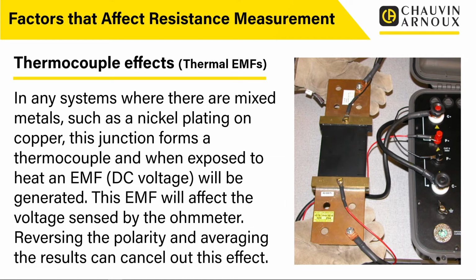Many testers, many micro-ohmmeters, include this automatic reversing function. They will measure one way, then measure the other way, and by doing that we get the average value. Where you've got to be careful with this is when we're measuring inductive loads. If we're measuring, say, the windings of a motor or windings of a transformer, these are inductors.